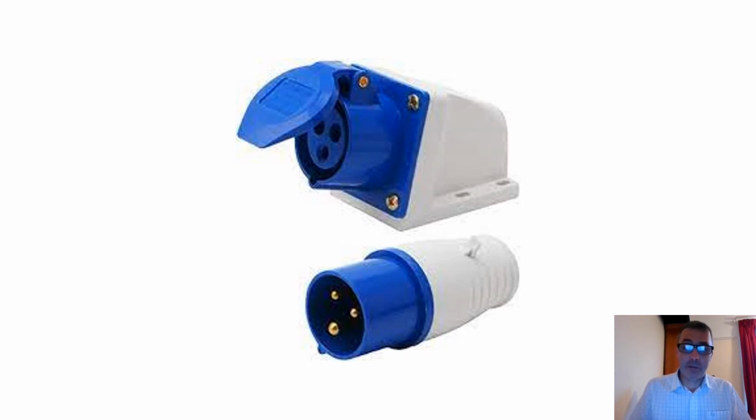The other advantage of this is you need to fit the corresponding electrical plug to the laser itself, which would stop it being used in rooms which haven't been checked for laser safety. So you could only really use it in a room with this kind of plug, and with an appropriate design that would only be the operating theatre that you've designed for safe laser use, or indeed another controlled laser area.